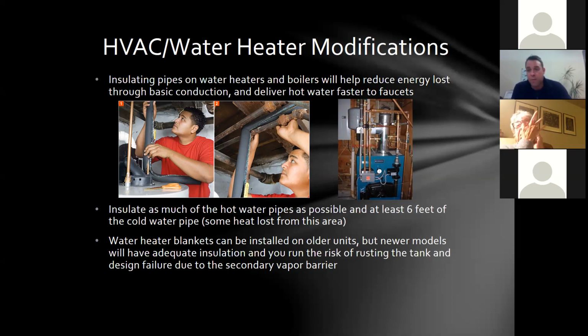Getting the hot side pipes insulated throughout the basement, if you can get to them — do all of the hot side, and at least 6 feet of the cold pipe, since there's some heat loss into that area, so it's good to get that to recycle. Definitely do all the hot side. And if you have a boiler with a sidearm to a holding tank, make sure you insulate that loop between the two — that's a big area of heat loss.